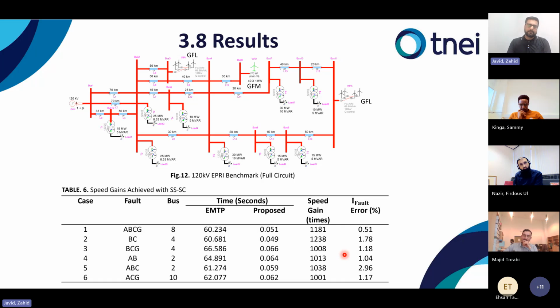And these are the results from the full IEEE 120 kV EPRI benchmark. We apply different faults at different buses, balanced and unbalanced, and we compare the speed with EMTP. With the proposed method, we achieve almost three orders of magnitude of speed gain, and the error in the fault current compared to the EMT is less than 3%, which I think is a very good trade-off for the speed.